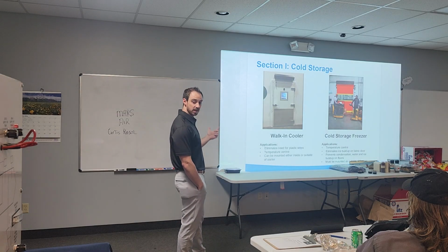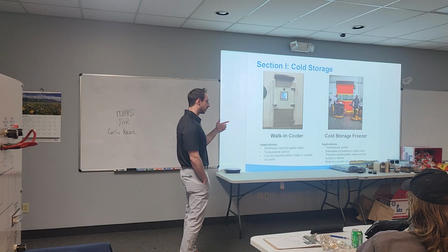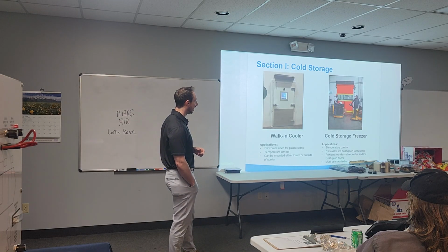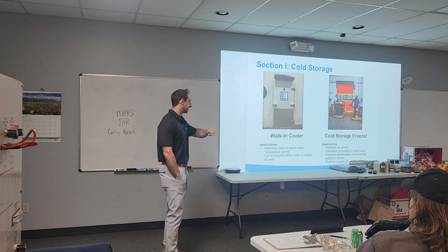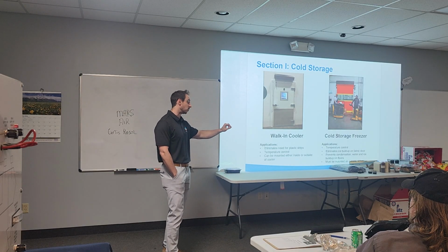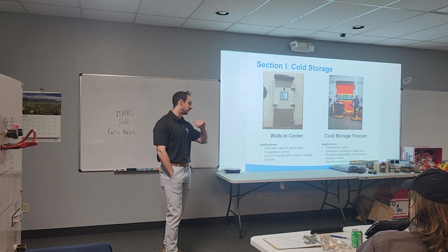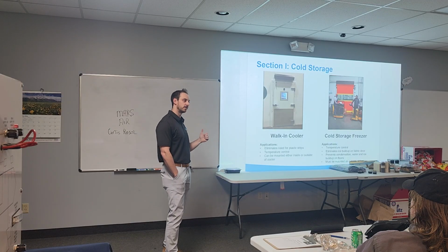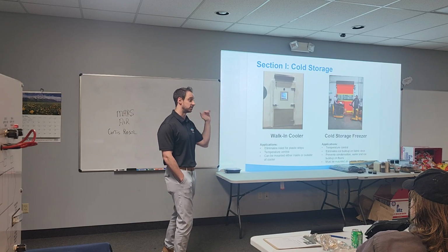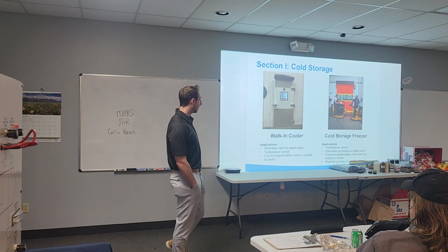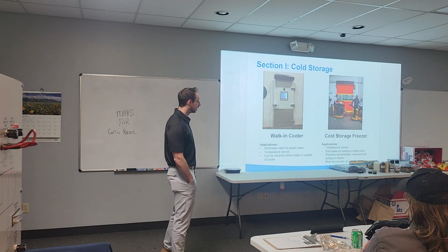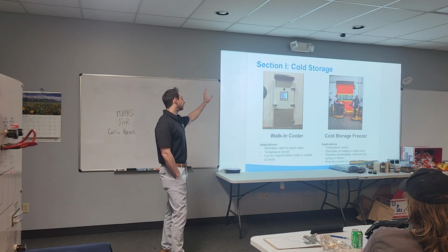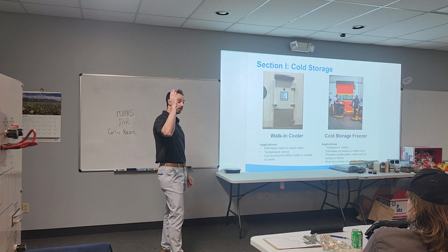There's a Campbell Soup project. I can show you guys that. It's on the PowerPoint, but I have another image of it. They had a problem where their forklifts were actually sliding on the ice buildup in front of the door for the cold storage room, and the forklifts actually crashed into the wall. They lost product, the forklift got a little damaged, and then obviously it's a safety issue. They can't see through the strip curtains. If they have strip curtains, those become dirty. So for that project, we actually did a vertical air curtain install.